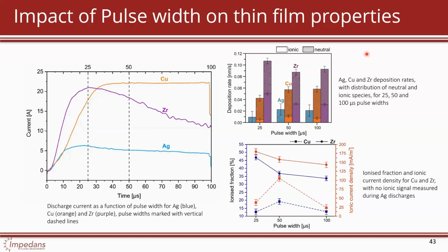Do you have any data validating repeatability of these sensors, assuming a stable, mature process and hardware? What's the variability of one sensor over time, and variability sensor to sensor? Very good questions. So we calibrate the electronics box and the feedthrough that come with these systems. For example, for the voltage sweeps, we use a 0.1 volt power supply, and they're calibrated over the range, so they're pretty good actually. They should be correct within about 1 volt. And we calibrate the current as well, and that's correct within something like less, we only ship it if it's less than 10 nanoamps offset. So we calibrate those two.